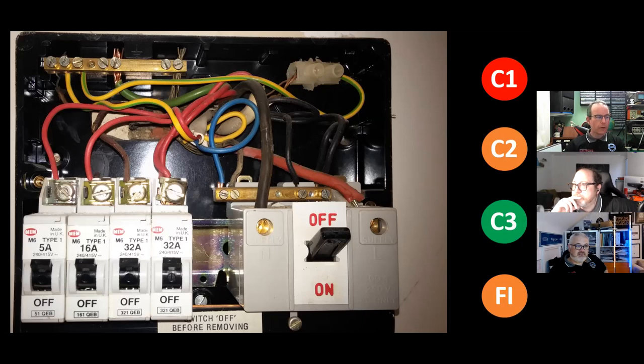It's within an enclosure, I'm assuming, with strain placed on the terminal. As a minimum, it's a C2. And then I look at things like the strain on that incoming main. What protection's on that? Is it a 60-amp service fuse or something?